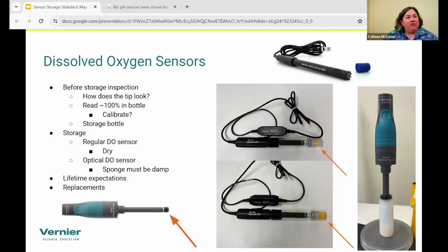And the other thing I like to do when I'm taking a look at these is make sure I take a good look at the tips, because that's where the actual sensing is going to take place. With the optical ones, it's a little more difficult to tell, but usually I see over time they get a gray haze on them and go from black to gray. That's usually one of my first indicators that it is time for that tip to be replaced.